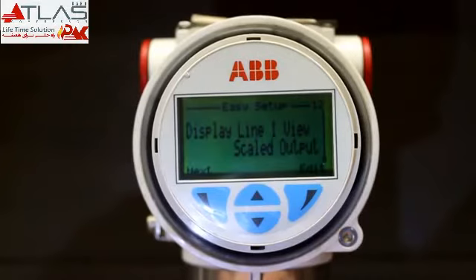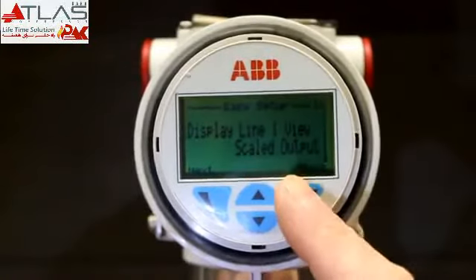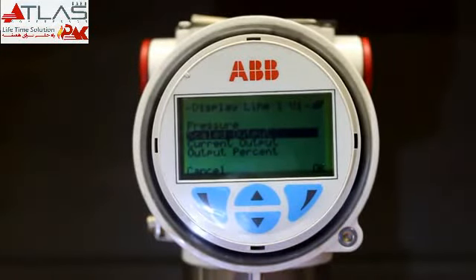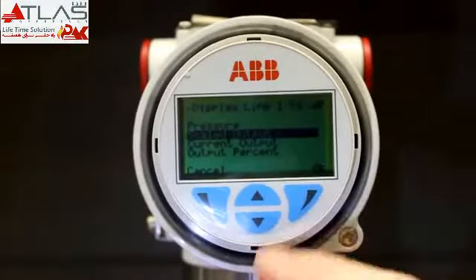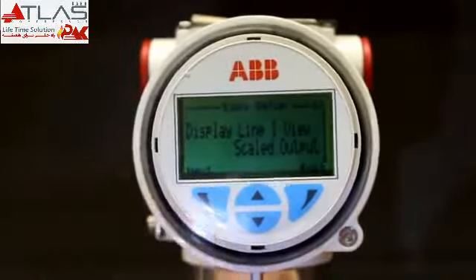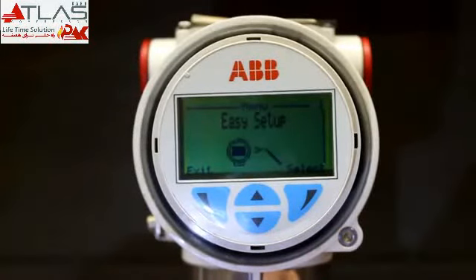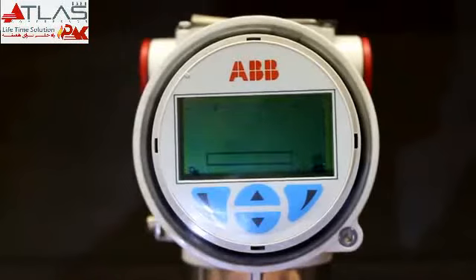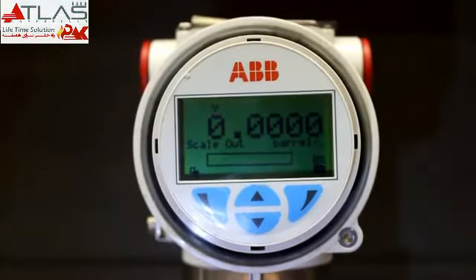Now we've got display setup here. Line 1 view is scaled output. If we edit, it gives you the options here. You can show the differential pressure that you're reading, scaled output, current output, which would be your milliamp output, or your output percent. We're going to leave that at scaled output and hit next, and that's it. Those are just the basic functions of the transmitter, the easy way to go through them and set them up. Right now you'd still have to set up your scaled variable for your scaled output for the display. Anyway, there you go.